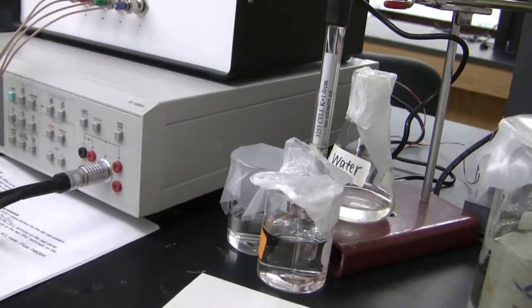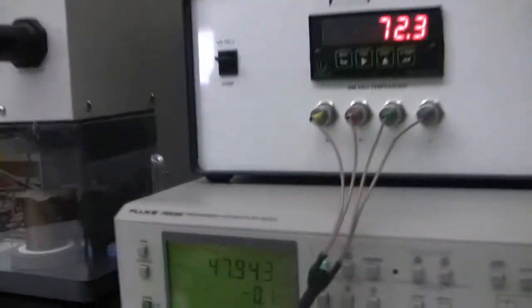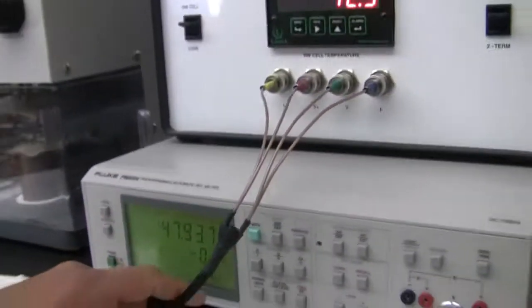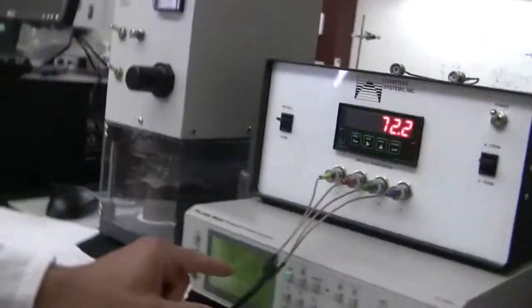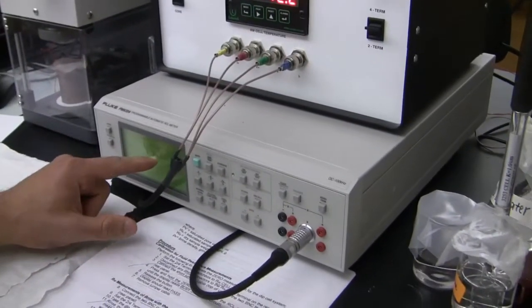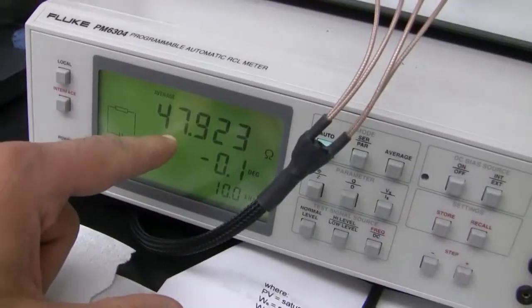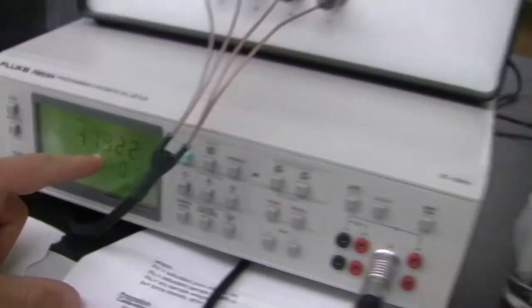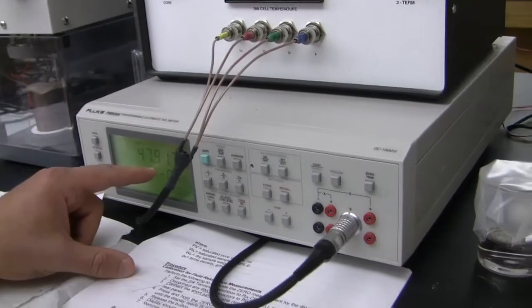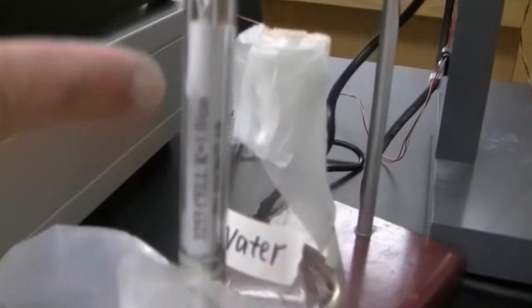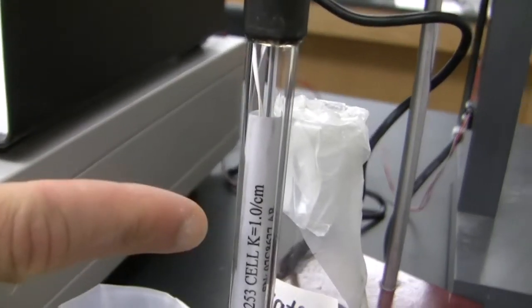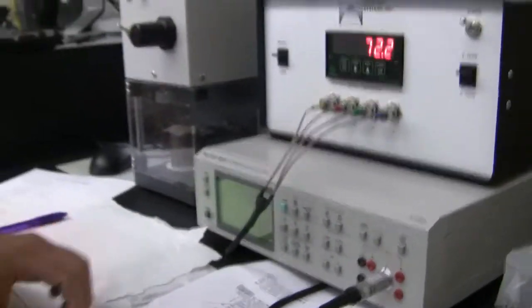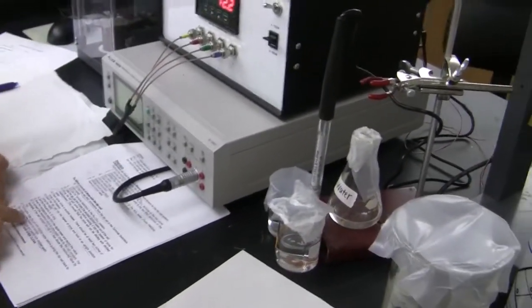After that, you make sure that the frequency here is 10 kilohertz, as you can see here. And then you record the value of resistance that you can see on the screen. This is your resistance in ohm. And if you want to convert it to ohm meter, you need to divide this by the cell constant. The cell constant is actually written on the cell for you here. It's 1 per centimeter. So when you divide this by this, you get ohm meter. Just convert this to meter instead of centimeter.